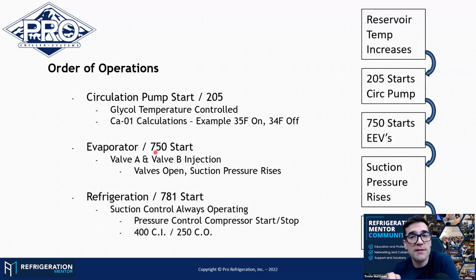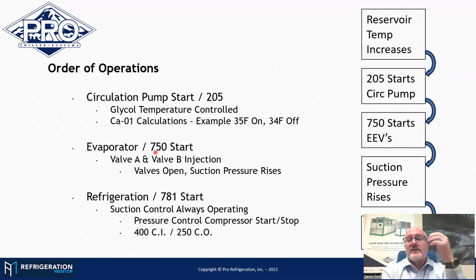So these are some of the things that, when you know the sequence of operation, are going to make your life easier and quicker when troubleshooting a system. You'll just look at your pressures, is what I do. I know in the back of my head that at 400 PSI this compressor should be running, whether the 750 is on or not, because the 781 is always watching that pressure. If we come up above 400, that compressor is going to start. If it's in an off cycle and we're getting some increase in pressure just from ambient conditions, it should still pull down and operate back down to hold it between that 250 and 400 range.